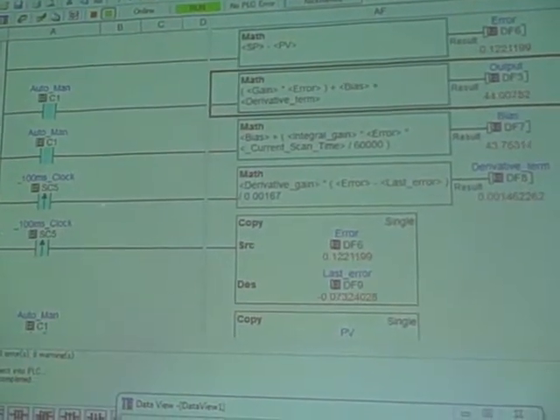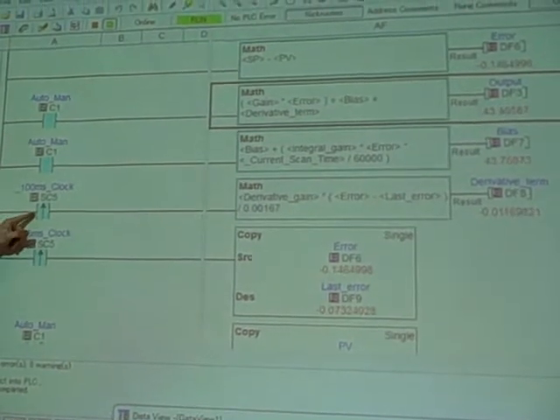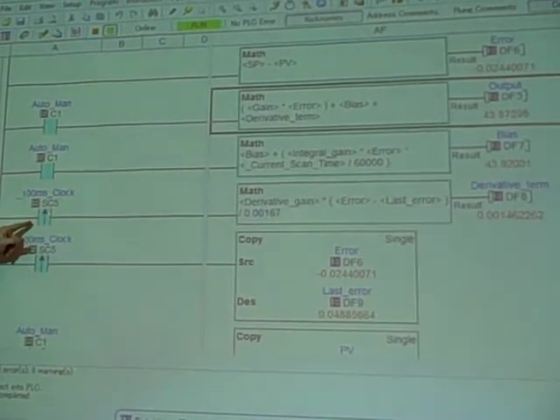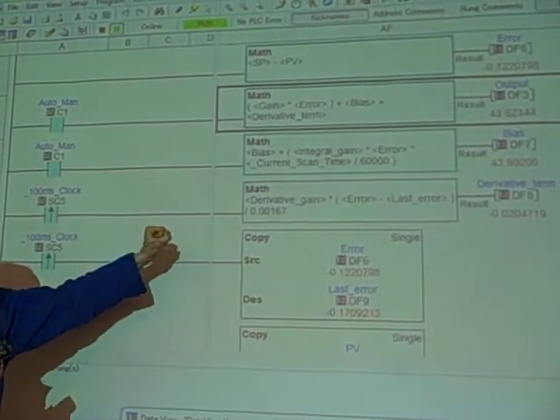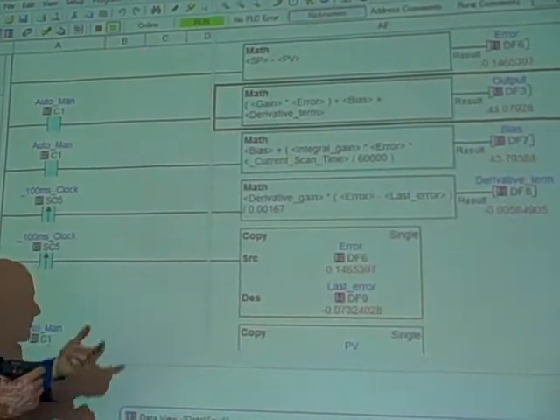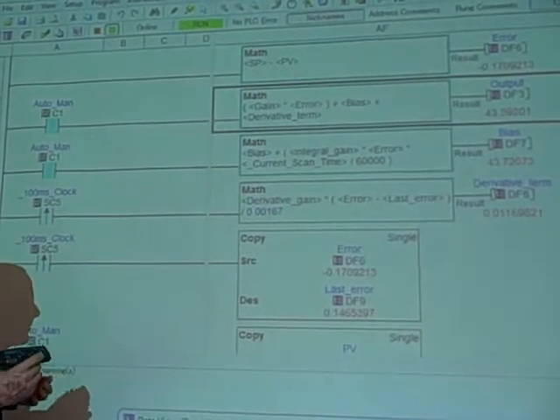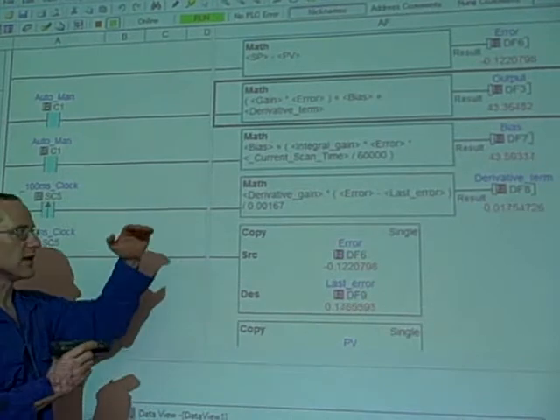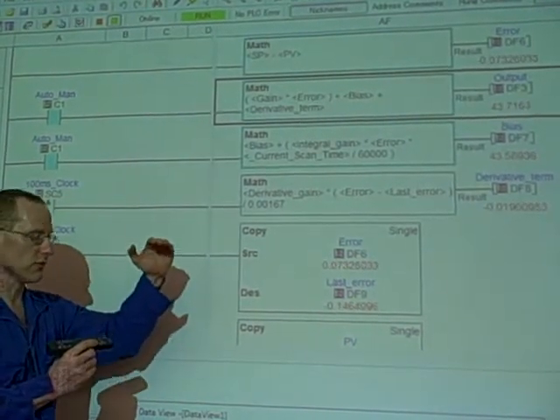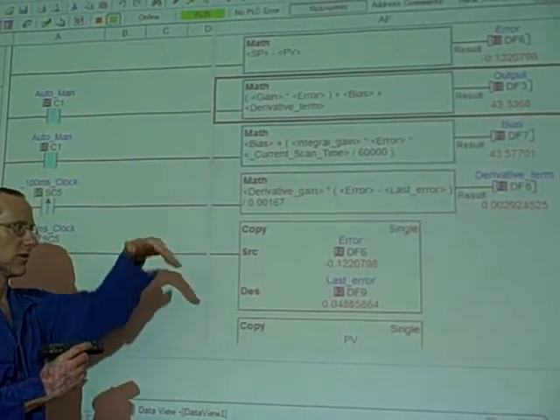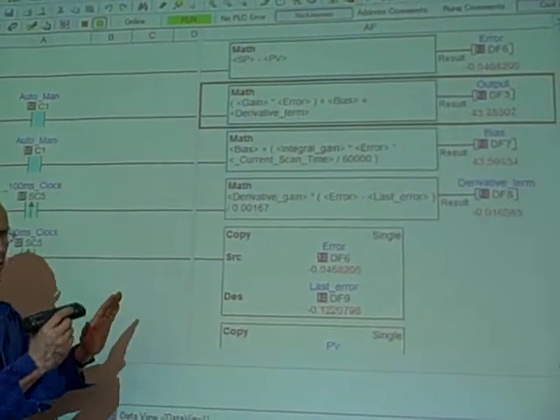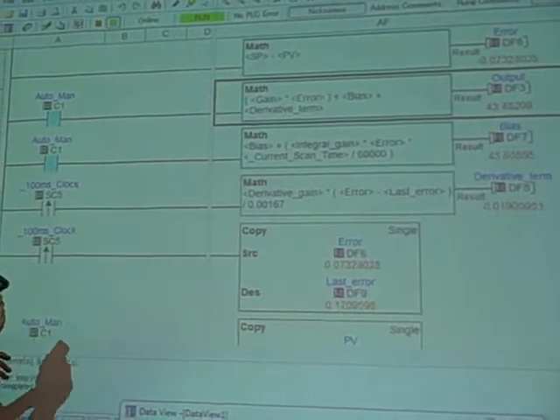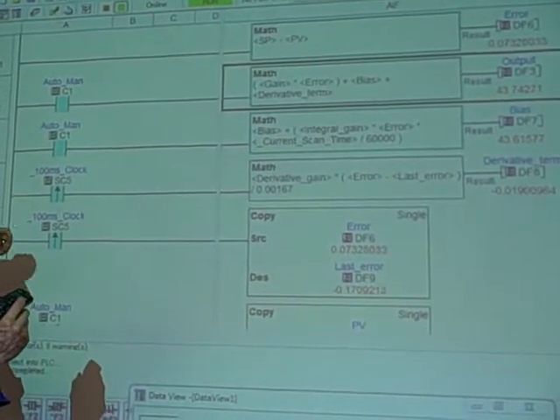This rung is activated or energized every 100 milliseconds, every tenth of a second, and that contact goes on the rising edge, which means we only take a look at the error and the last error and calculate rise over run every tenth of a second. We do that for a very specific reason. If we did this with every single scan, what would happen is every tiny little bobble, every tiny little jostle of the process variable over time would be interpreted as an extremely high rate of change, which would basically make our derivative term blow up.